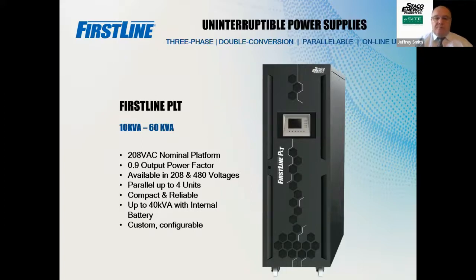The UPS systems that we offer in 3-phase, these are my products, are the 10 kVA through 60 kVA. The platform is basically 208 volt, 120, a 3-phase 4-wire system as standard. In this configuration, we're able to put up to 2 transformers, an input and an output. Or in some cases, it could be 2 inputs if you're looking for a dual input system where you have an input transformer and a bypass transformer. Up to the 40 kVA size system, we can put up to 2 strings of batteries in here. That's one of the nice things. So you get runtime, you get batteries, and you can change the voltage if you need to. Next slide.